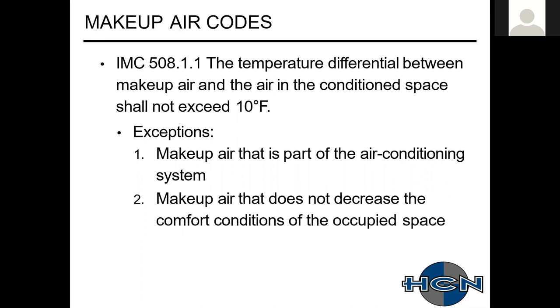So that replacement air is exempt from tempering so long as the comfort cooling/heating system can compensate for that additional load. The big thing there to look at is that it can compensate for that load. So you really want to avoid using that exception if you can, because it's less problematic to temper at the source.